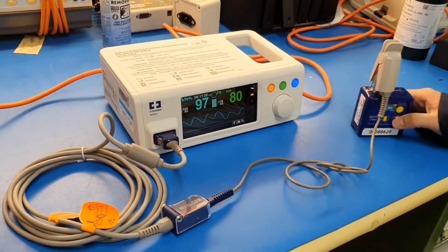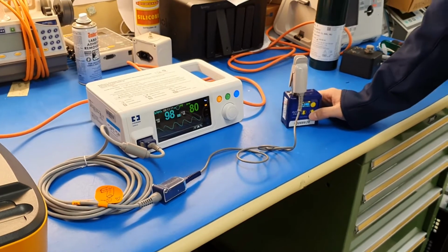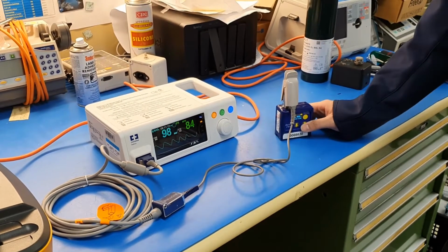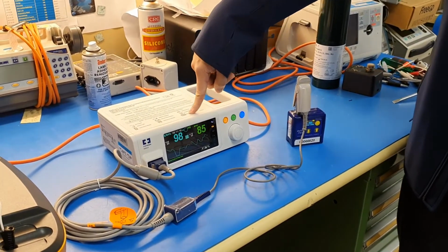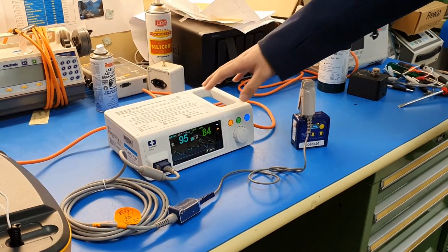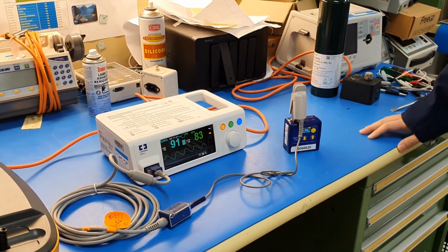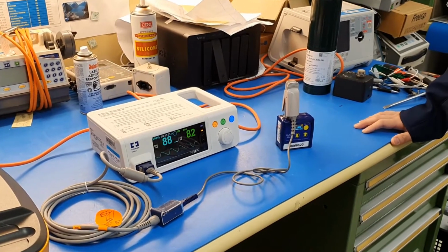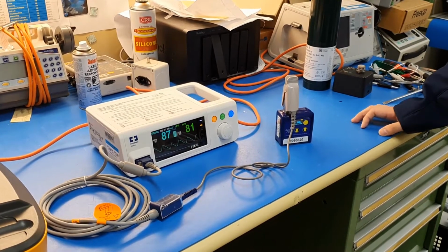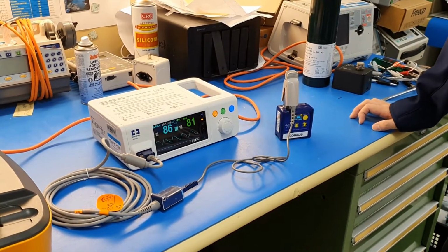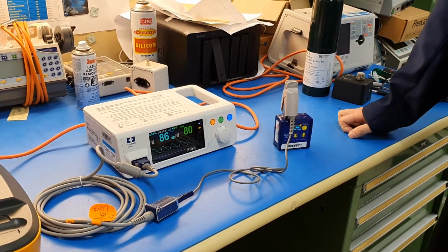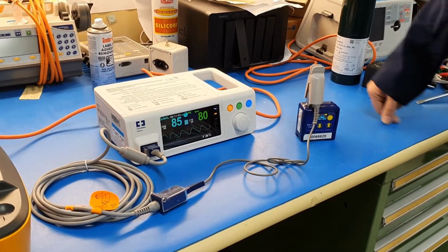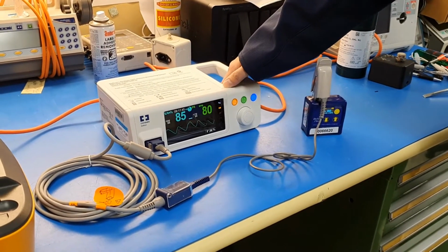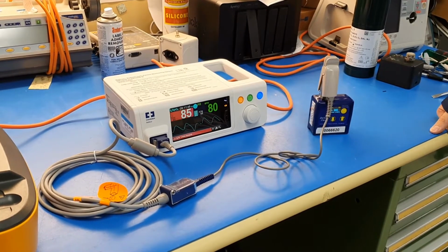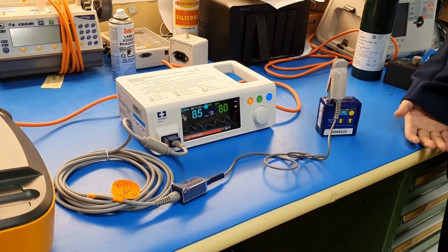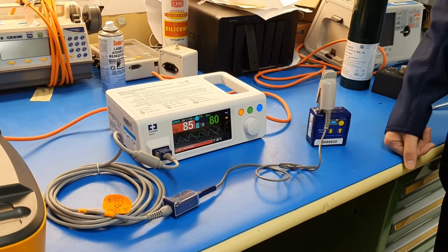And what we will commonly do when we do testing is we make sure that it will alarm once those parameters are outside of the alarm limits, as shown here, just so we know that when it's used on a patient, we can flag anything that is abnormal. So we should expect it to alarm soon. There we go, and now we know that it's safe to use. We also do common tests like electrical safety to make sure that it is safe to use in patient areas.